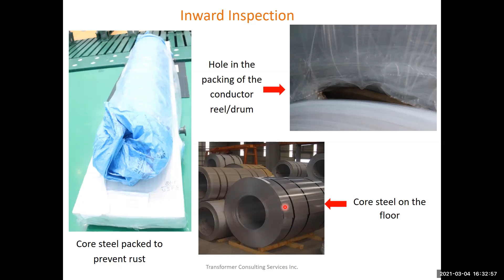Here is an example. On the left-hand side, you see the blue thing being wrapped. Inside is pre-cut steel. The pre-cut steel has been oil soaked and wrapped properly so that when it is shipped, if it rains during the monsoon, it's not going to rust. Not only that, it's not going to collect any dust. On the right-hand side, this conductor reel was shipped with a hole, and through this hole monsoon water got in and contaminated the conductor. On the bottom one, you can see that a core steel roll is lying on the factory floor and is being dented. Any of those things can compromise the quality of your transformer, which you cannot foresee.